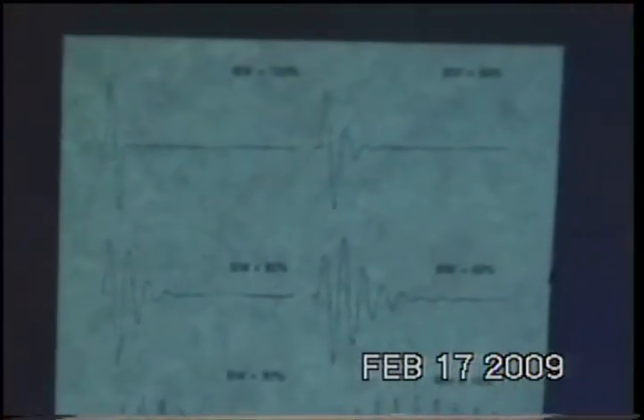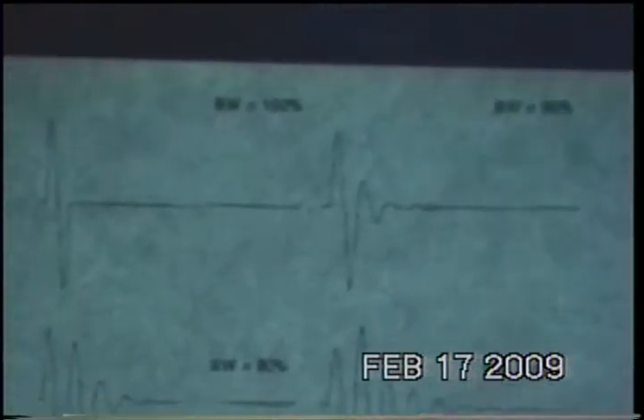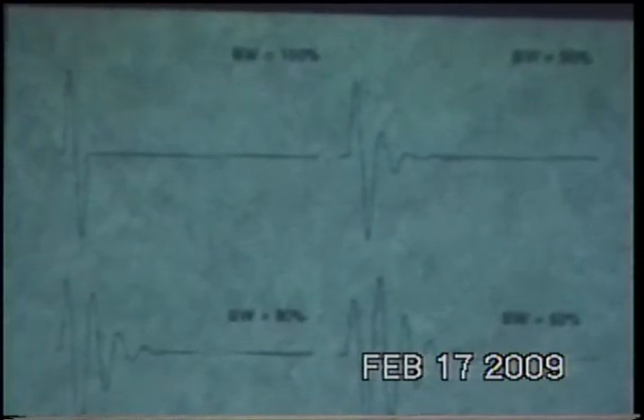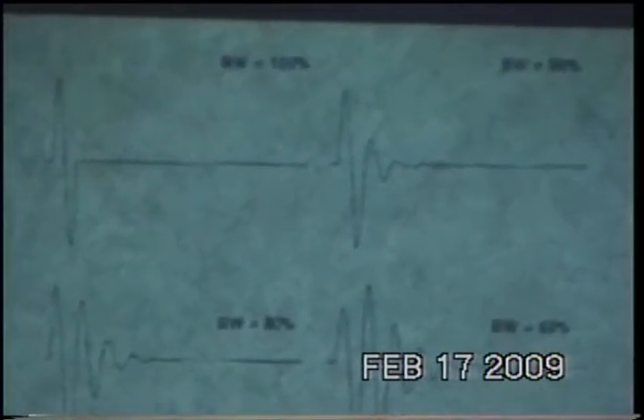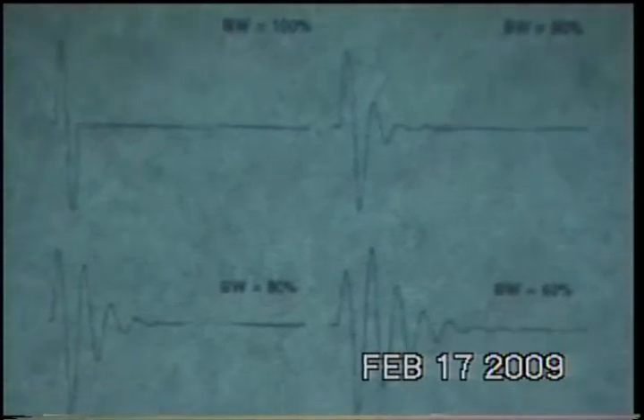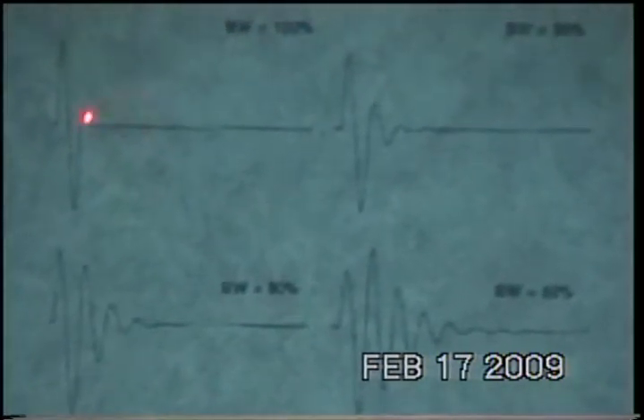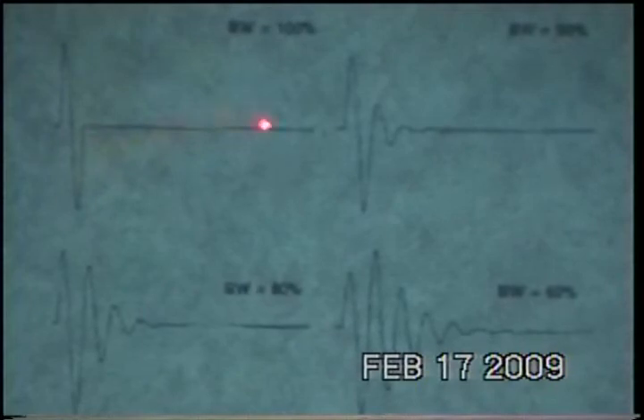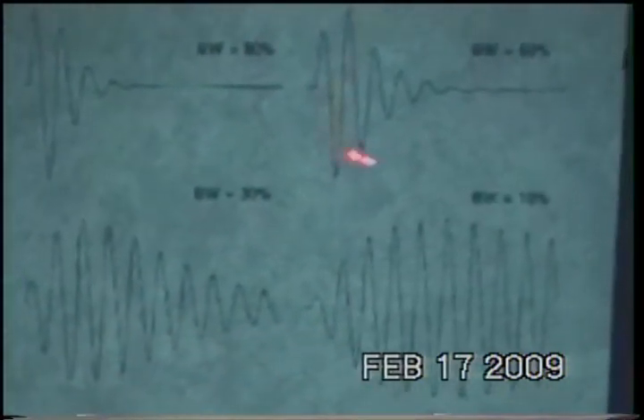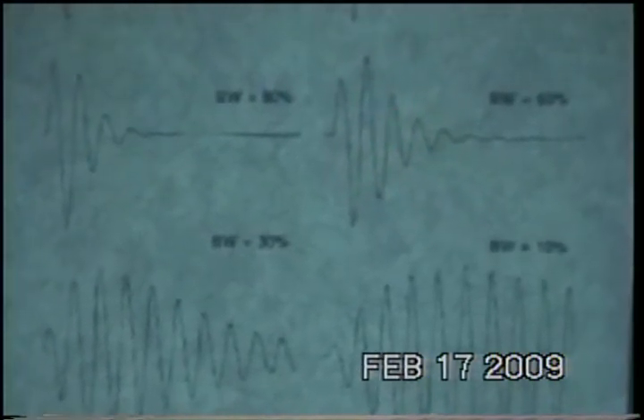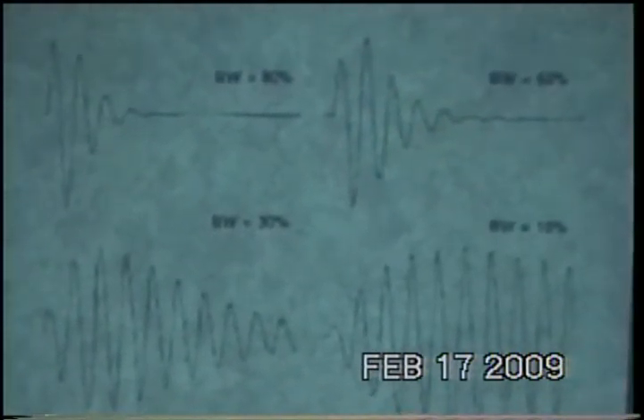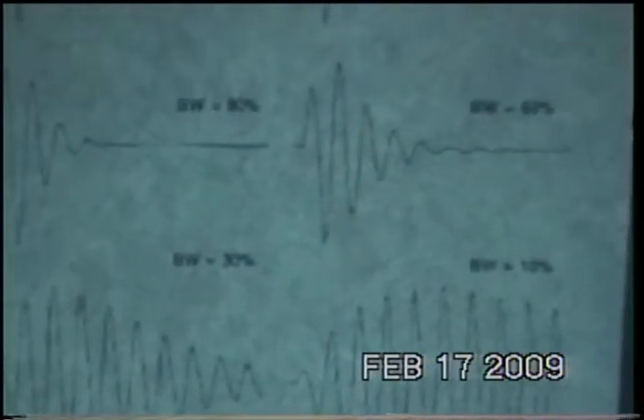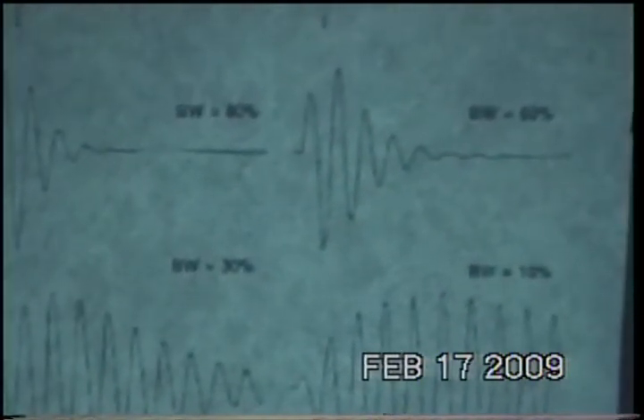Your critical flaw size determines what frequency and bandwidth you want your transducer to have. Here's an example of some bandwidths, all the same frequency but using different bandwidth percentages, from 100% down to 10%. A standard, middle-of-the-road transducer typically has about 2 to 2.5 cycles, around the 50% range.